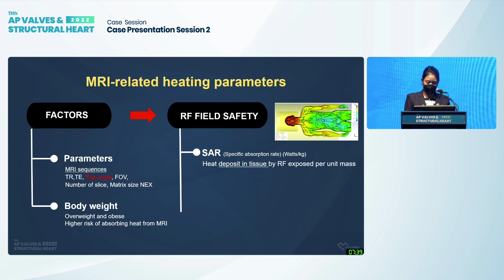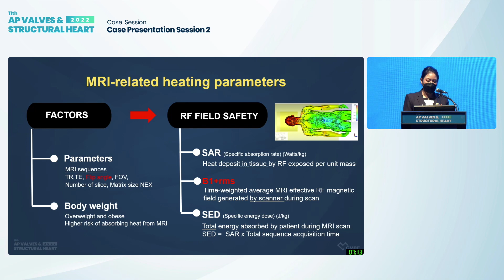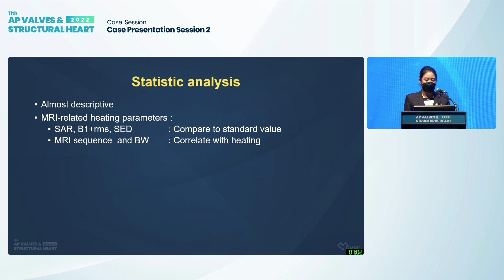The second is the B1+RMS. It's the time-weighted average of the MRI effective field created by the scanner during the scan, and it depends on the MR protocol. And the last one is SED, meaning the specific energy dose in joules per kilo, which is the total energy absorbed by the patient during MRI. So we analyzed descriptively and compared to the standard values accepted by IEC, and correlated with heating from MR sequence and body weight.